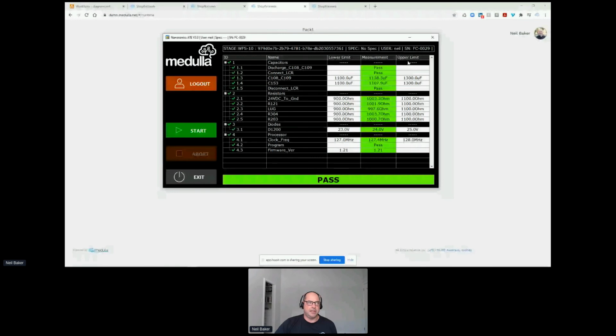And that goes back to the mentality earlier, or the frustration, where you sometimes get this test until pass concept. By exposing how close it was to the boundary and knowing that some of these values might have some fluctuation, if I was to just test that again, it's quite likely that it might pass. So if you have three fails and one pass, does that make your product good? These are some of the checks and balances that we're really trying to make sure that businesses follow, really good standard business process.